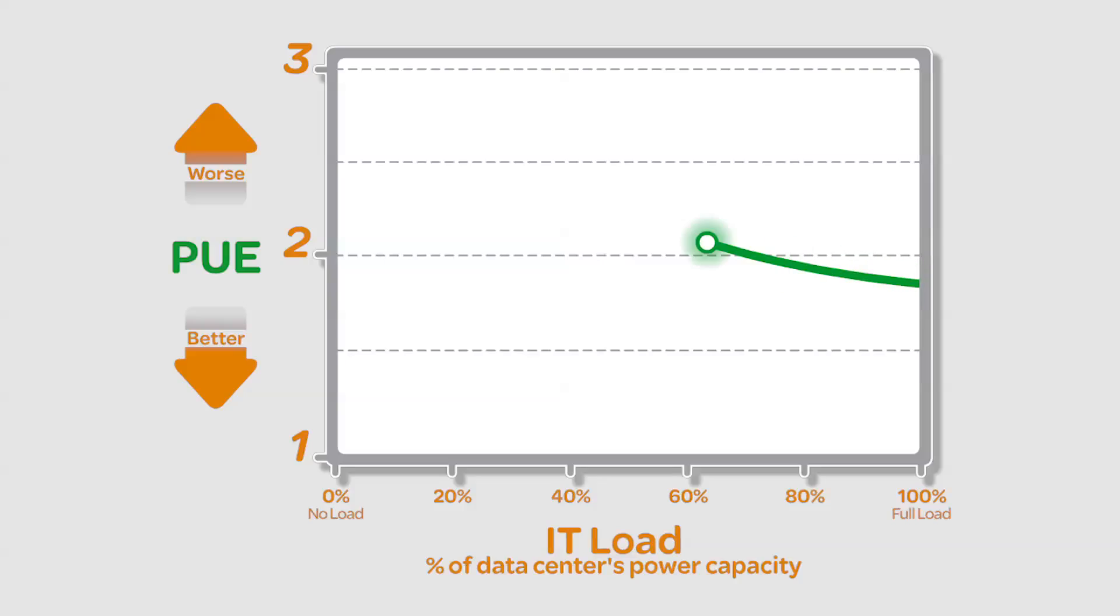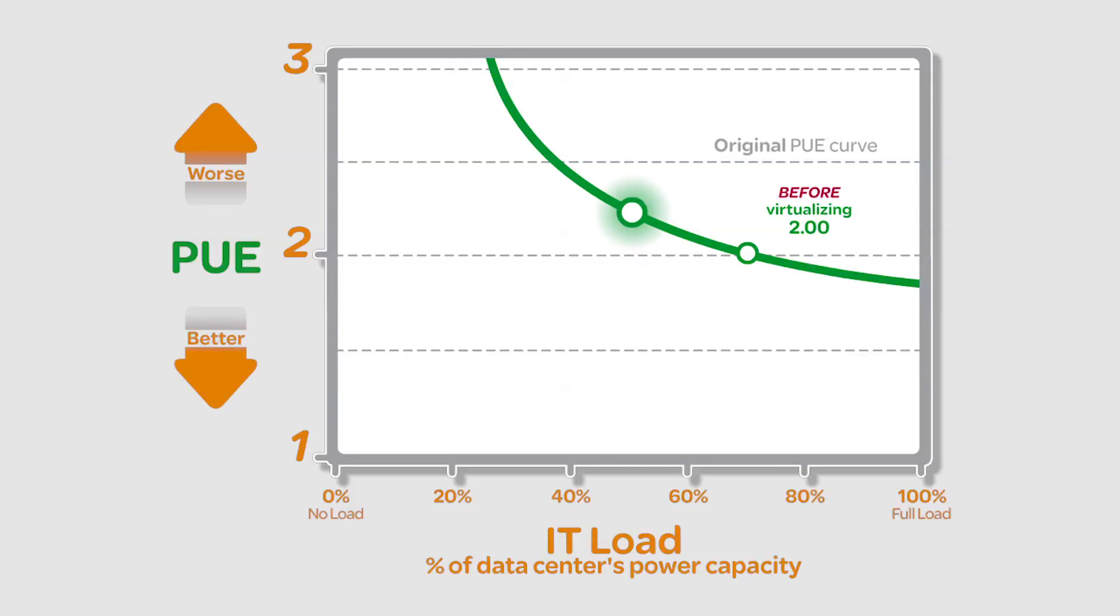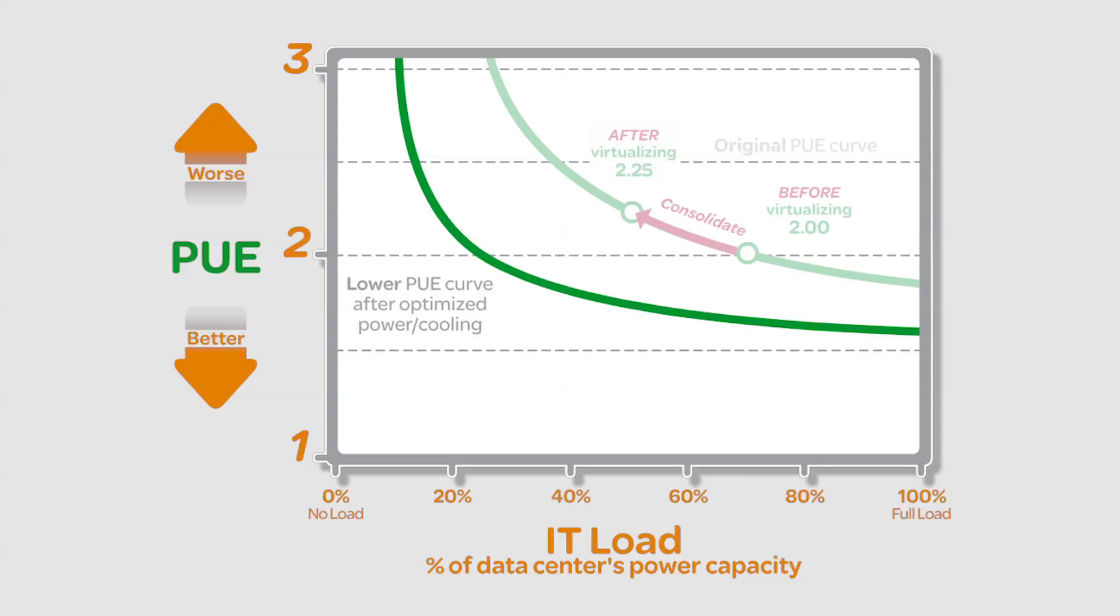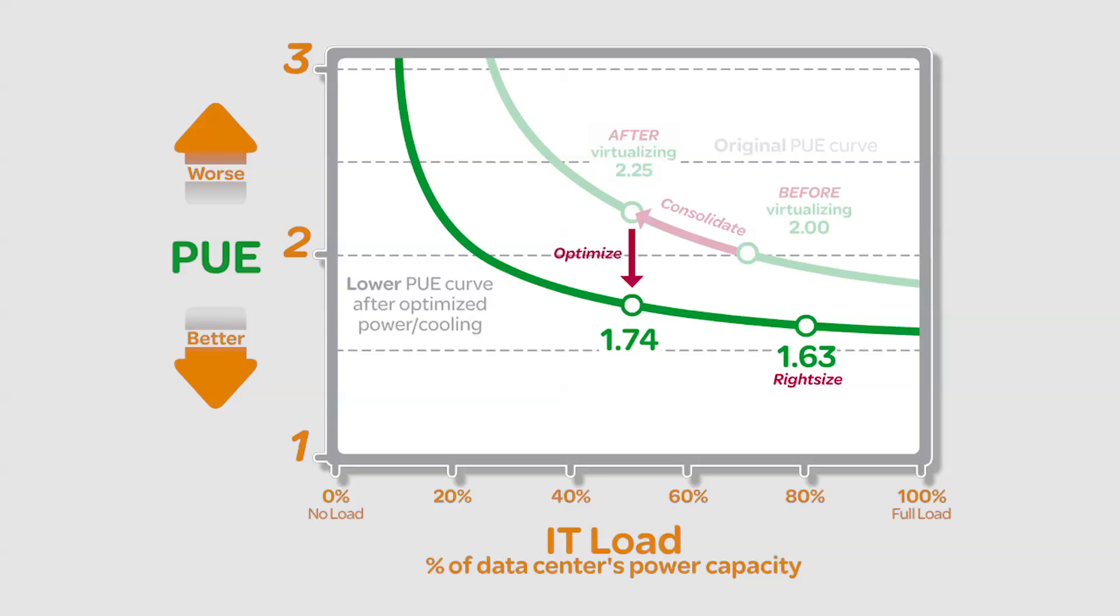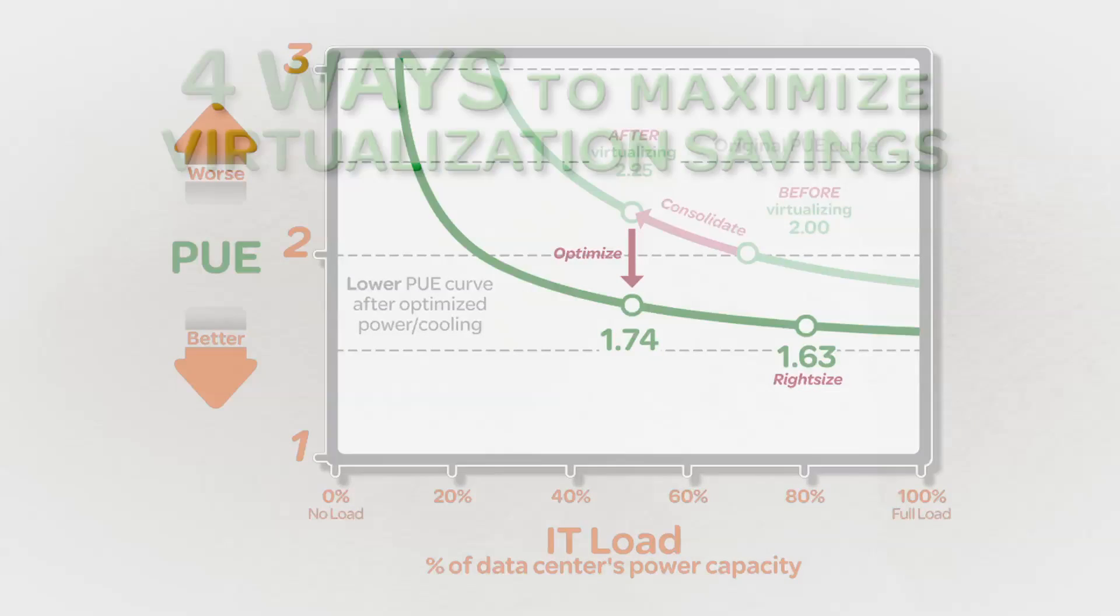For instance, did you know that virtualization can actually worsen your PUE? Here's why. Virtualization reduces IT loads, leaving existing power and cooling infrastructure oversized. This can degrade your PUE significantly and may lead to disappointment in how much or how little your energy consumption is reduced.